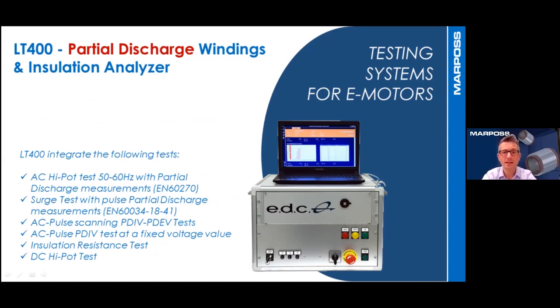A scanning test that is a particular function in which we can apply to the unit under test an increasing voltage, AC or pulse, up to detect the inception voltage and the extinguish voltage values. The value of the inception voltage found with the scanning test allows to determine the optimized voltage value to perform the PDIV test in production.